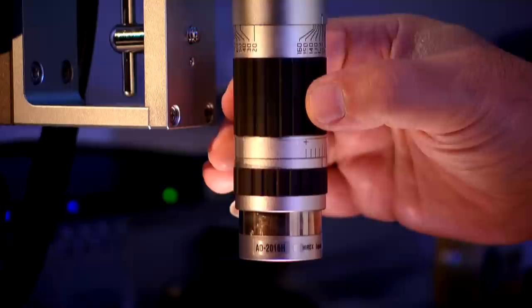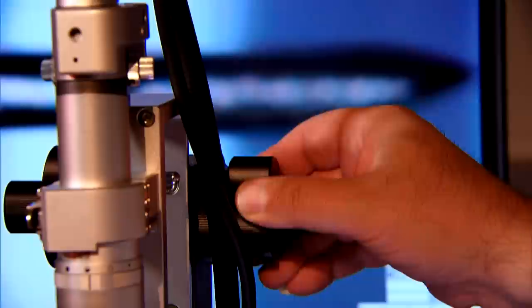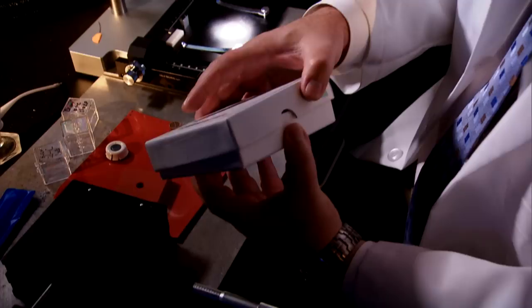He investigated the Huber needles to determine if we had a design problem or a manufacturing problem. The first question I asked myself was: how do we test the needles with a lap band port to see if they create cores? We looked for and discovered that there was no standard design parameter for testing ports with different needles. So we designed our own test. A major part of our effort was to come up with a test that we could validate and share, so that manufacturers and our own internal organizations could reliably reproduce the test and believe the data. We had to determine whether this was a problem with one batch of needles or with all needles that were made.